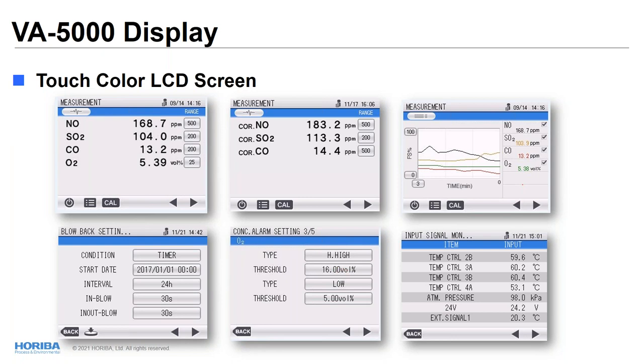And concentration alarm settings: you can set the concentration alarm for each parameter, like high, high-high, or low, low-low alarms, and set the certain concentration to trigger the alarms. And finally, this display is showing much information about the analyzer inside the body. We are tracking all of the temperature of the cells, the voltages, and the pressures, stuff like that. All of this information is very, very useful for your diagnostics.